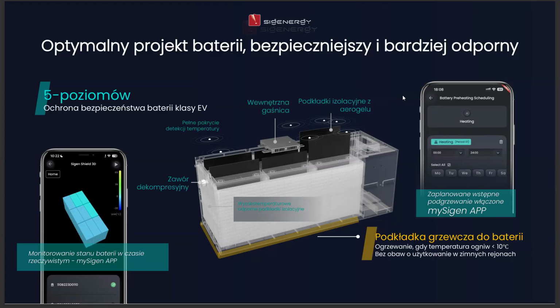System level, inverter and batteries are shut down. Building level, with the Sigen gateway, the entire building can be isolated with a single button. By opening the contactor, the building is disconnected from all power sources, allowing firefighters to intervene safely. This gives full control over whether only the device is shut down, or the entire building installation is isolated.